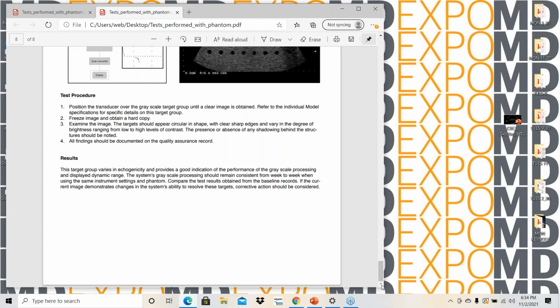Are those saved as a test file? You can save them as a test file. You name the patient, for example, PM ACR, American College of Radiology. So now you know the customer, you did a PM, but you did it in conformance with an ACR, or just PM. And then you can save it to their server, and then you can recall it 6 months later to compare your results. Or you can do printouts. And then just make sure if you're using a thermal printer, you keep them in a spot that's not super hot. You can put them underneath the cosmetics, but not inside the computer because it gets much hotter inside than outside. So it is a thermal printer as such. So keep that in mind.